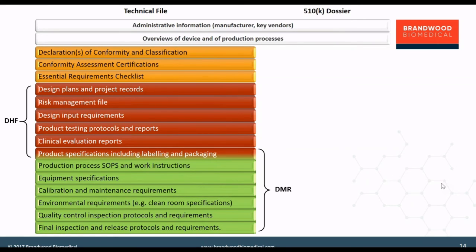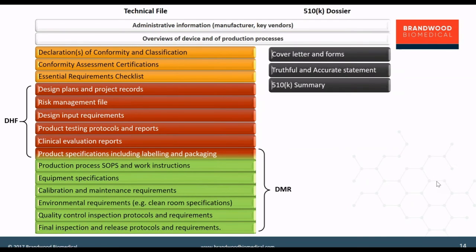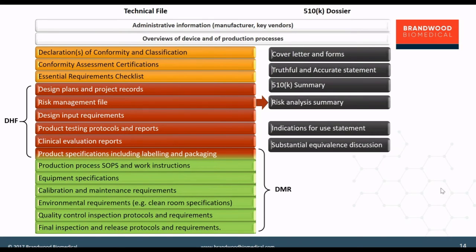On the other side of the pile, let's have a look at how this technical file fits into the 510K technical dossier. The first three boxes here are elements which are specific to the technical dossier, but then the rest is naturally flowing from the DHF.